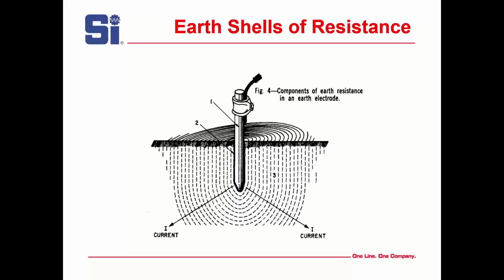So when we look at grounds, we take a metal conductor and we insert it into the ground, usually with a hammer, if you're like anybody else. And what that does is create ground earth resistance. The earth resistance is considered to be equal width. So as it spreads out, if you look at these circles, or half circles, you can see that they're getting bigger and bigger. So your highest resistance is right here, and as you go away, you get lower resistance. Well, you insert current through your ground bar.